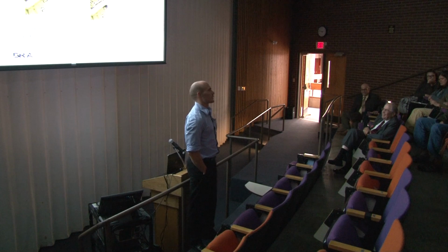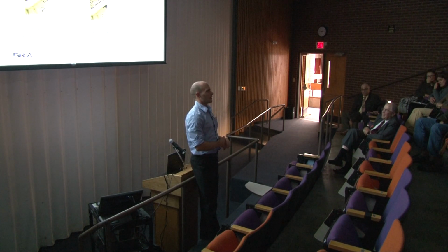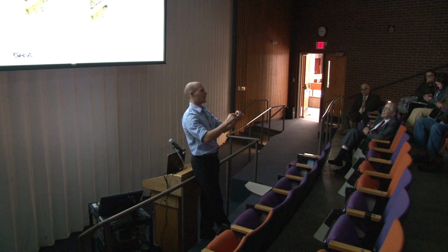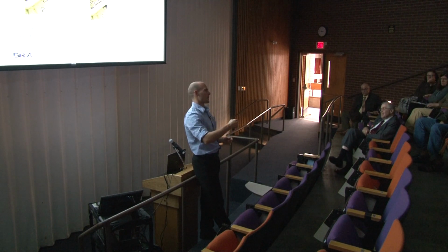Yeah. So the thermostats are applied in each zone, which is almost every space in the building, and each has its own temperature control. You can have some plus or minus to the standard set point for that zone, and the standard set point can also be shifted by the facility staff. But the really exciting thing about these thermostats is that the screen itself lights up a different color, at least for the spaces with operable windows, to tell you when you want to be in natural ventilation mode or in mechanical conditioning mode. And so it'll tell you when you should open your window for the spaces where the windows are manually operated.